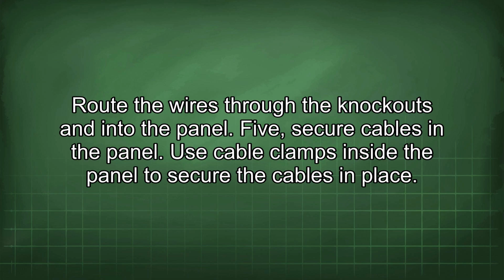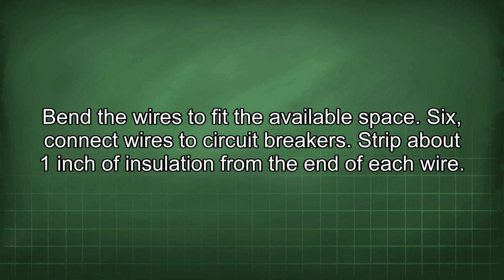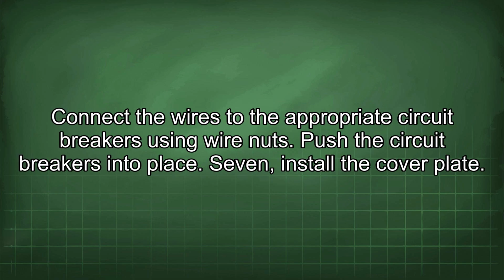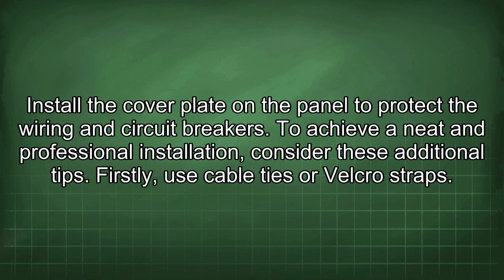5. Secure cables in the panel. Use cable clamps inside the panel to secure the cables in place. Bend the wires to fit the available space. 6. Connect wires to circuit breakers. Strip about 1 inch of insulation from the end of each wire. Connect the wires to the appropriate circuit breakers using wire nuts. Push the circuit breakers into place. 7. Install the cover plate. Install the cover plate on the panel to protect the wiring and circuit breakers.